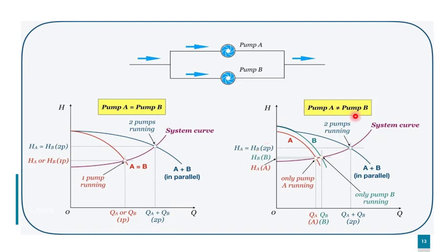In the second case, everything is the same. The total head, and the total flow will be the sum of the two pumps, but every pump has a different configuration curve, that means different flow and different head. But in total, at the operation point here, the head is equal for both configurations together. It is giving one head, but it is giving the total flow of the pumps, QA plus QB.